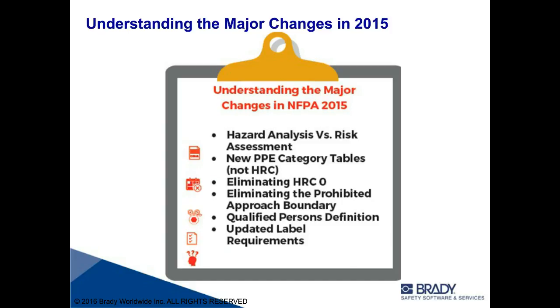To note, as part of that, they also eliminated HRC 0. HRC 0 was essentially removed because anytime you're outside the arc flash boundary, it's less than 1.2 calories per centimeter squared, and that was HRC 0. So even though they dropped that actual category, people still need to wear general PPE. If you're at 1.2, you still need to be protected, wearing your non-melting, all-natural fibers, but they just dropped out that category.